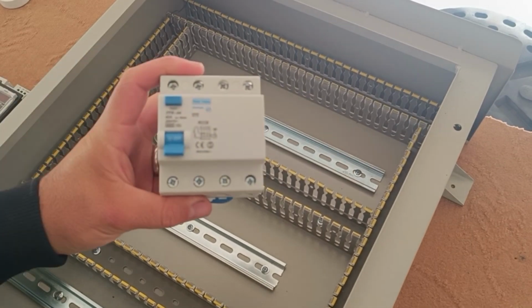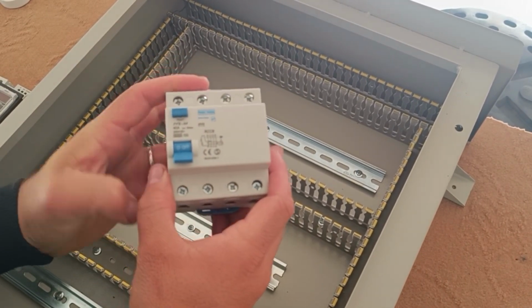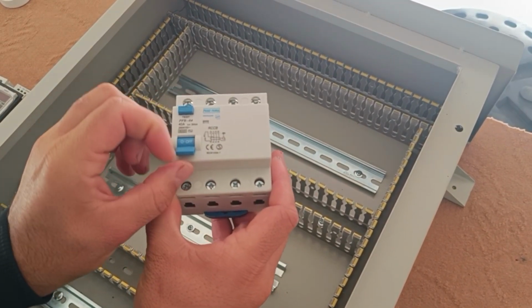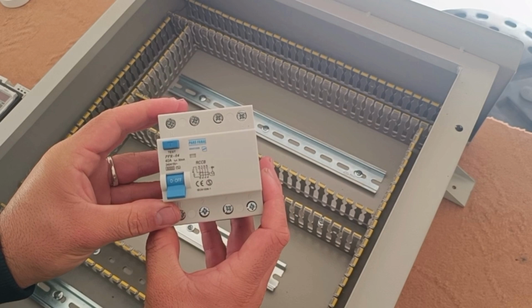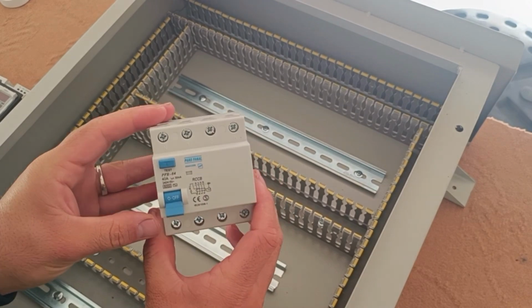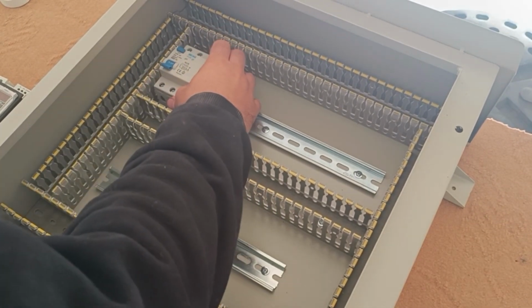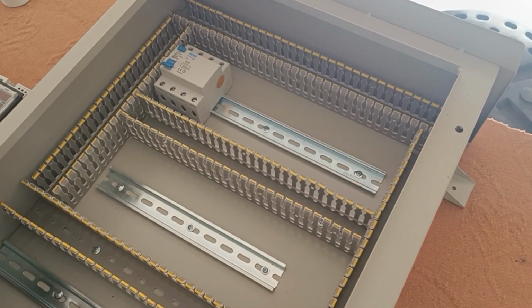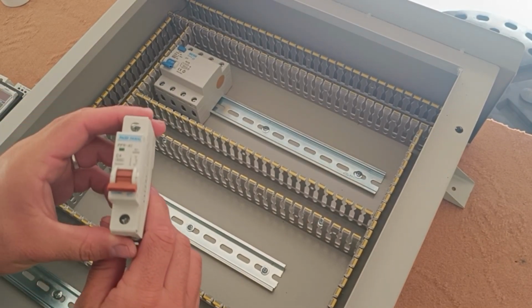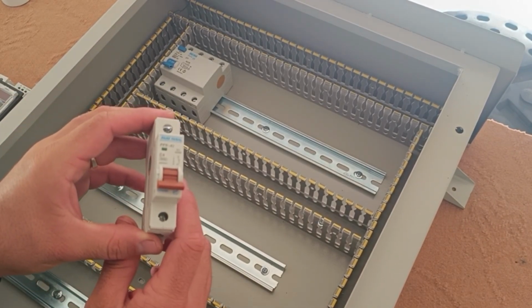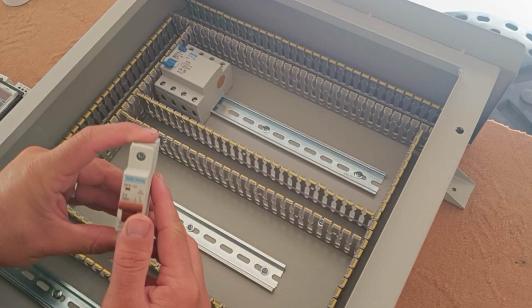The first device is a three-phase RCCB switch. This switch is used as the main switch in the electrical panel and supplies power to the entire panel. This switch protects the circuit against electrocution or electric shock. The second switch is a single-phase miniature circuit breaker that supplies power to the control circuit.